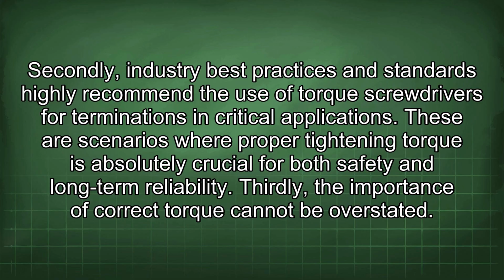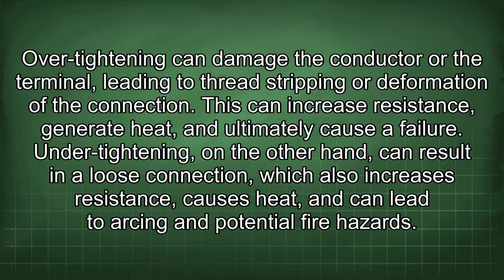Thirdly, the importance of correct torque cannot be overstated. Over-tightening can damage the conductor or the terminal, leading to thread stripping or deformation of the connection. This can increase resistance, generate heat, and ultimately cause a failure. Under-tightening, on the other hand, can result in a loose connection, which also increases resistance, causes heat, and can lead to arcing and potential fire hazards.